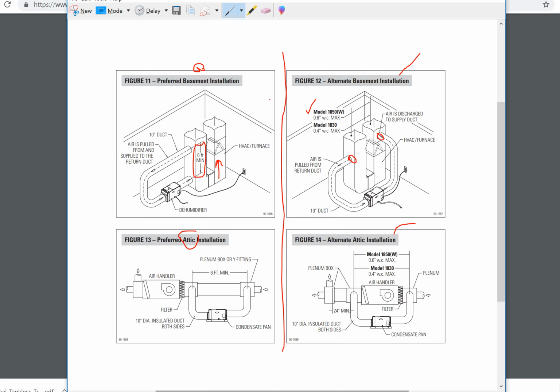So we prefer to do the installation where we go from return to return, so the air gets sucked out by the dehumidifier blower and then redistributed back in. At that point, the air goes through the normal cycle, through the air handling unit, through the cooling coil, and then off into the space with cold discharge air. That's the recommended way. It works better and everything works more efficiently that way. And that's how I do it at my house as well. So any questions, let me know, but that's how we do it. Return to return is the preferred method. Return to supply is acceptable, but has some disadvantages.